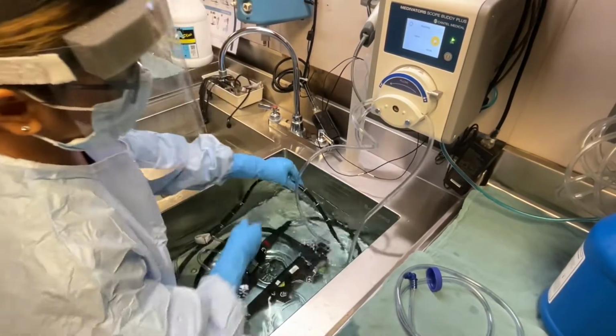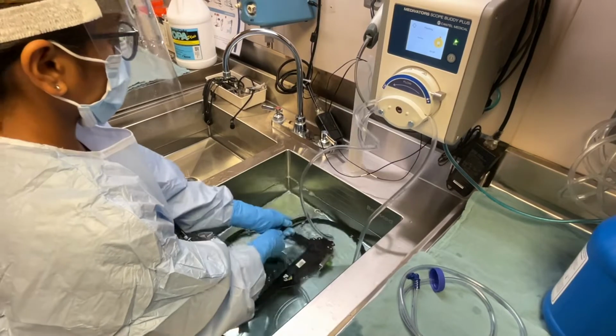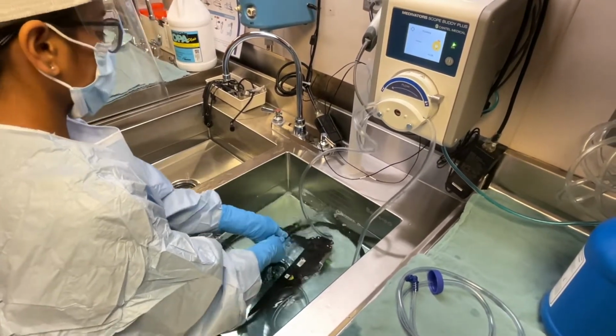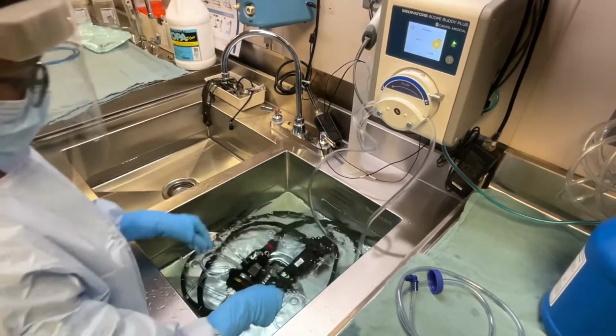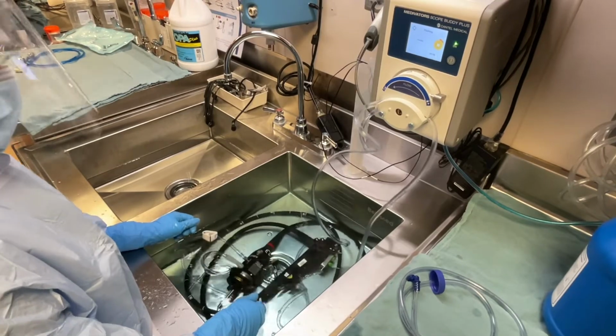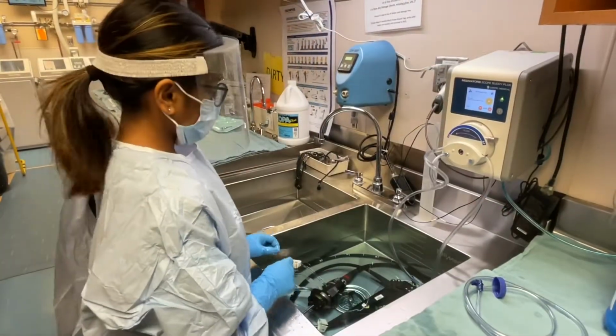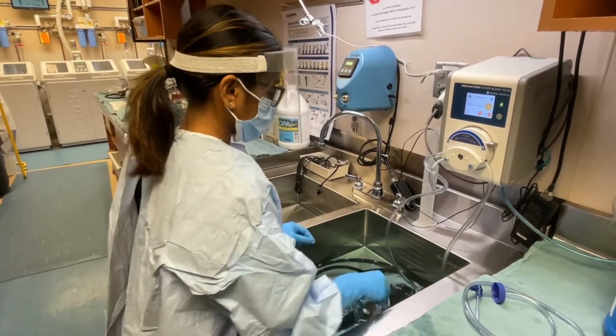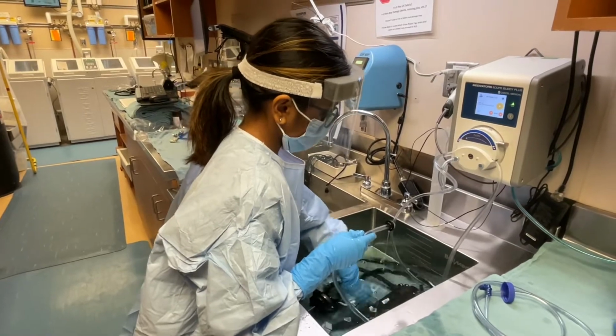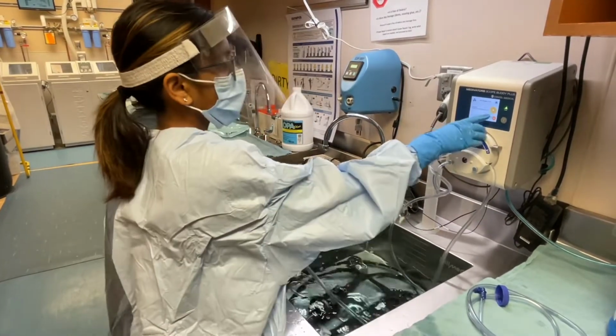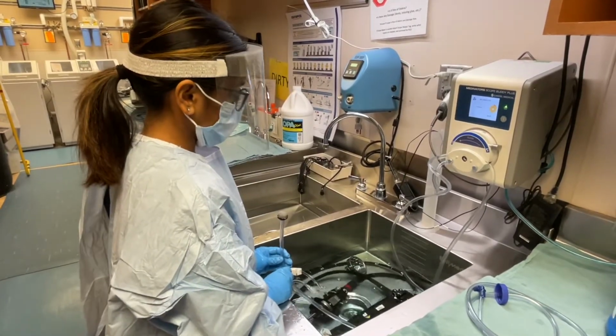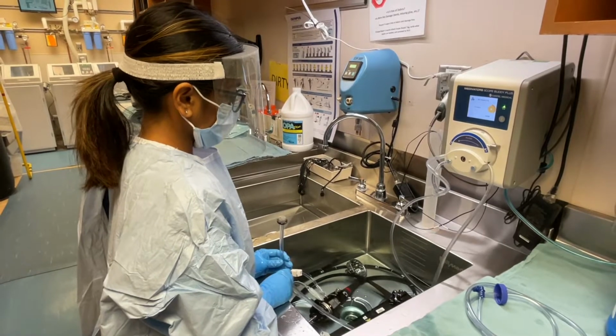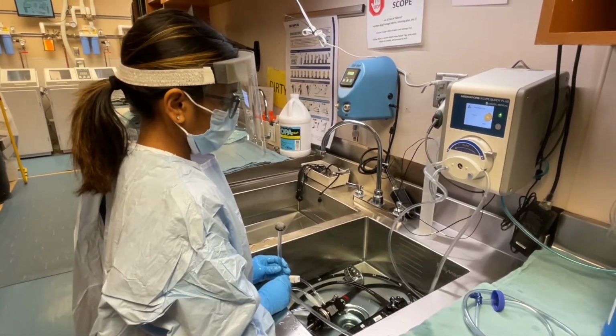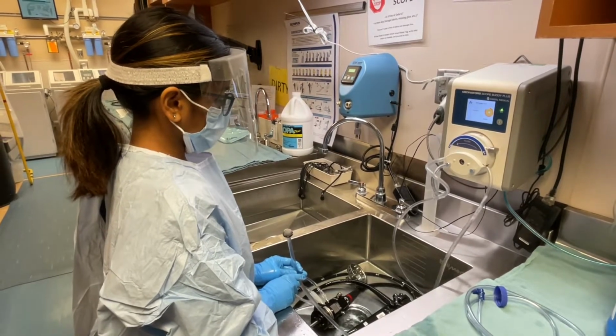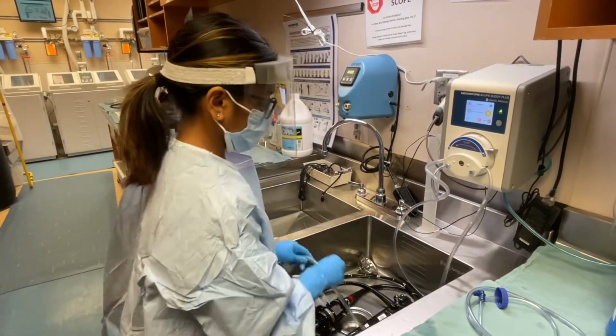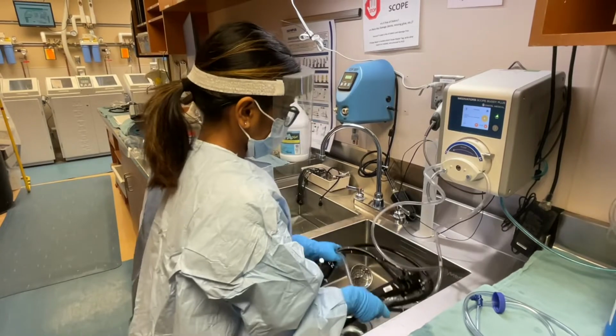Visually verify the solution is exiting the end of the scope. If it fails to exit the end of the scope, recheck your connections. If the fluid still fails to exit the end of the scope, contact a supervisor. Purge the endoscope. Lift the strainer out of the fluid, drain the sink, and press play. Move the scope and scope buddy lines to the rinse sink.